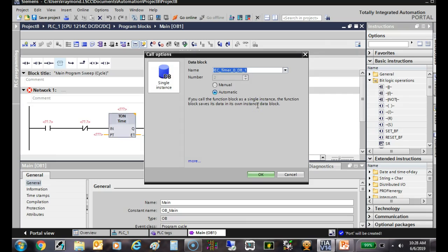And here, remember, this system does not assign memory until you try to use something. So originally, there's nothing assigned to timers. In RS Logix 500, you already have memory that is specified strictly for what? Timers. And there's 256 of them, 0 through 255. That memory is already taken care of. Those blocks are already set up.